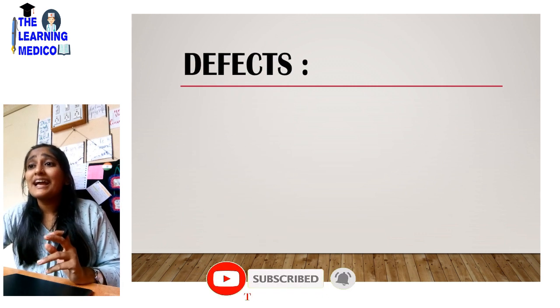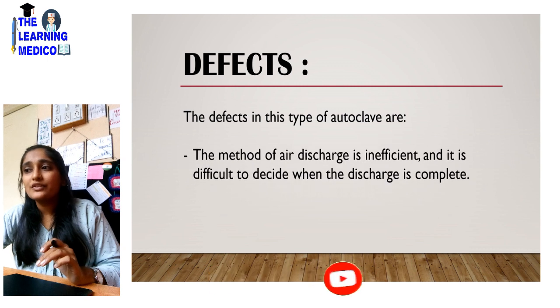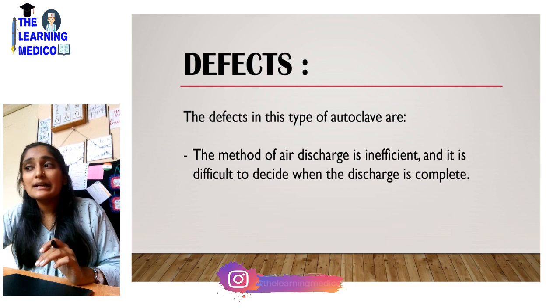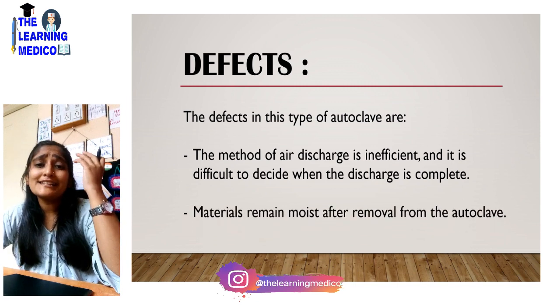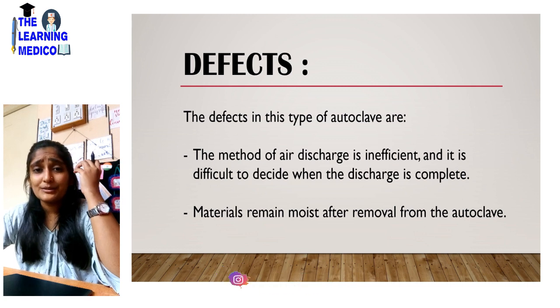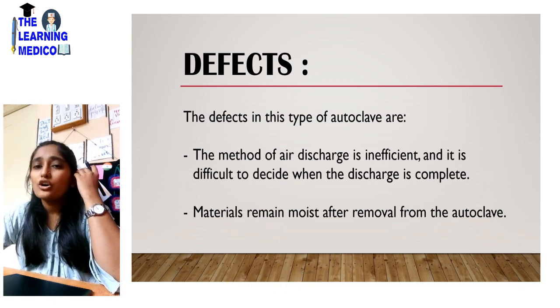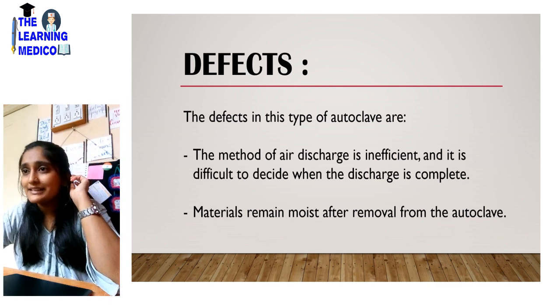The defects of this type of autoclave: the method of air discharge is insufficient and it is difficult to decide when discharge is complete. The material remains moist after removal from the autoclave, which means moist heat sterilization leaves the material more moist and the material may be damaged.